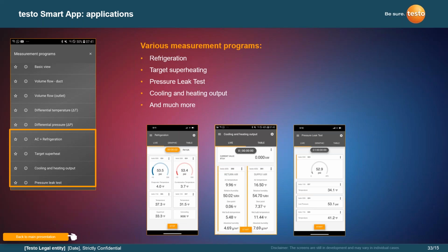You can put this quick test together with two 605i psychrometers. You need to get your airflow, and it will give you the BTU output of that system at that airflow. The airflow reading needs to be pretty accurate in order to get an accurate capacity reading.